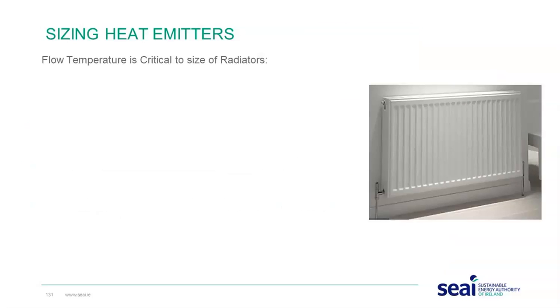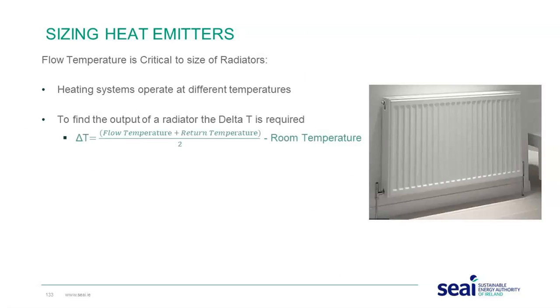Typically, I want to talk about radiators and sizing radiators because the flow temperature is critical to the size of the radiator. Different heating systems operate at different temperatures. So when we look at a radiator, to determine the output, we need to know what the delta T is. How do we find the delta T? It's the average of the flow and return temperature less the room temperature. Take a non-condensing boiler: typically a flow temperature of 75, a return temperature of 65, and a room temperature of 20 degrees. That gives a delta T of 50 degrees.